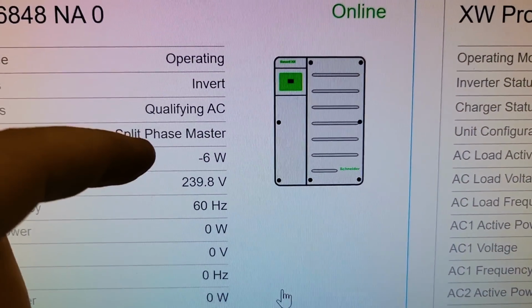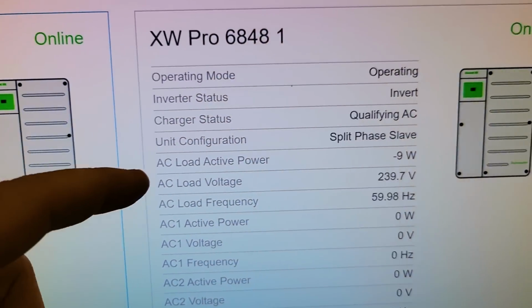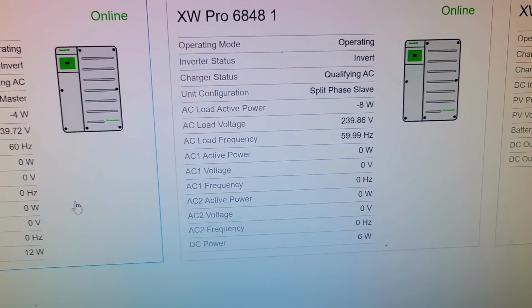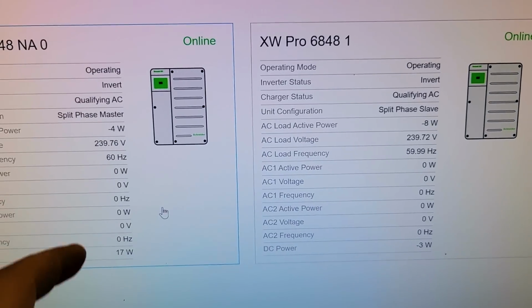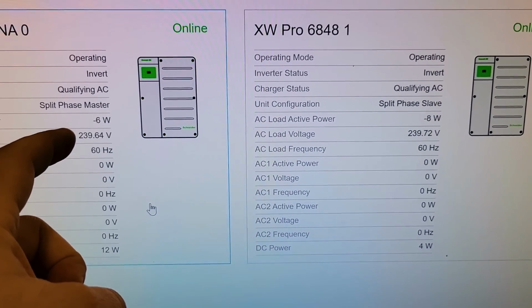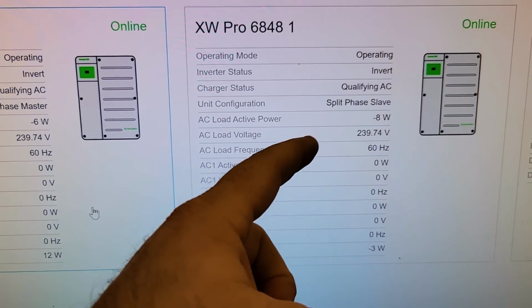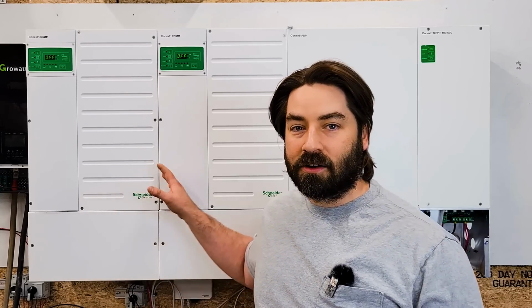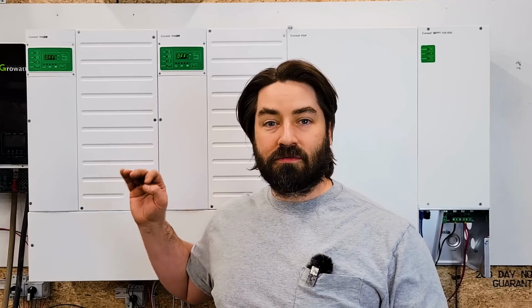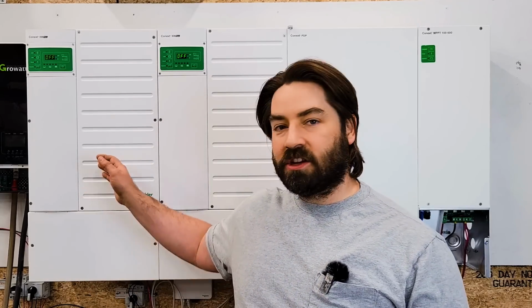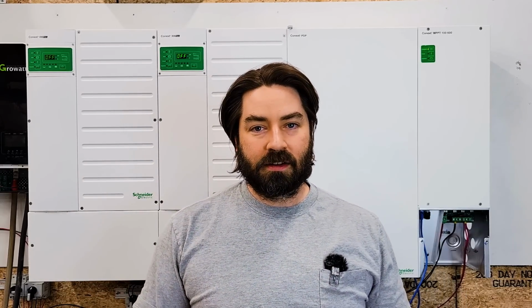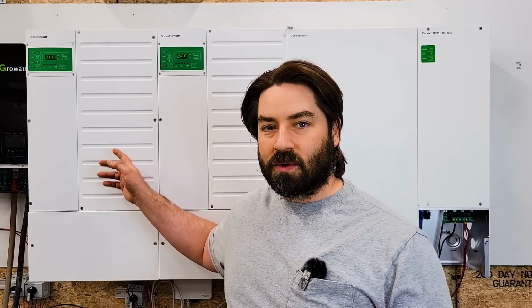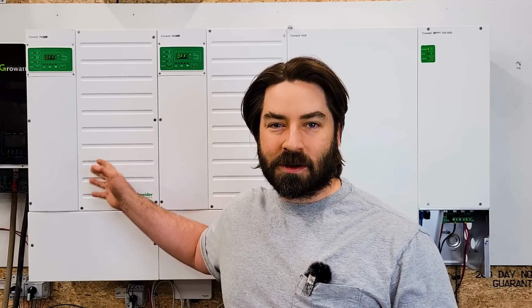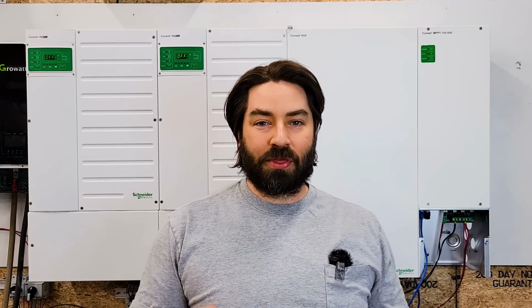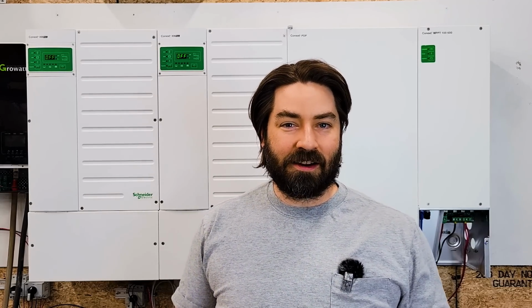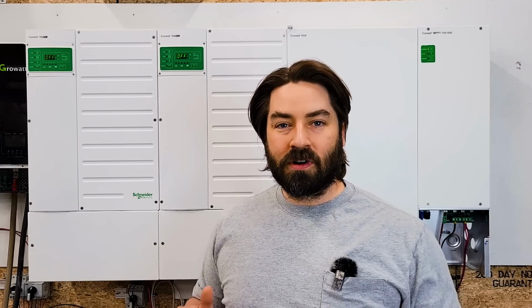Then when I turned on the circuit breakers again with no load, I went back and looked at the Insight Home, and now they're sharing the load evenly. There's no hidden loop of 100 watts. So they were both doing what they were supposed to do. It looked great. They idle at a very low wattage. These inverters are really excellent for their tare loss. I think each inverter draws 34 watts in idle, but these are 6.8 kilowatt inverters with a 12,000 watt surge capacity each. So having 34 watts of tare loss at idle, that is really, really good.